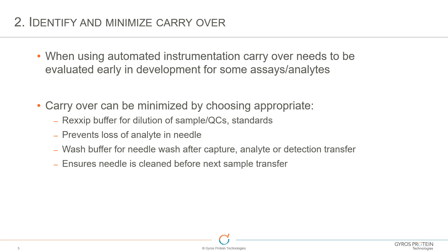In addition to that, we're pushing for greater and greater sensitivity, and people often look at very broad dynamic ranges. When you push to very high sensitivity assays, you exacerbate the problem of detecting small carryover. If the needles aren't absolutely clean between transfers, you can see a little bit of residual sample left on the needles. Using the right wash buffer helps ensure needles are clean. We have two wash methods that help mitigate the problem — the second wash buffer at pH 11 is normally used to minimize carryover.